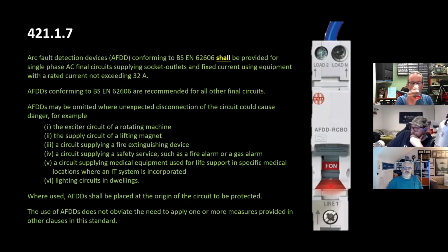This is the problem, this is general socket outlets, white goods type stuff. But there's nothing in the regulations that says that, it's just all circuits. Can I buy a washing machine that says Type B RCD? There's nothing in the regulations that says don't put it on circuits that require Type B. We'll get on to RCDs, but AFDDs conforming to BS EN 62606 are recommended for all other final circuits.